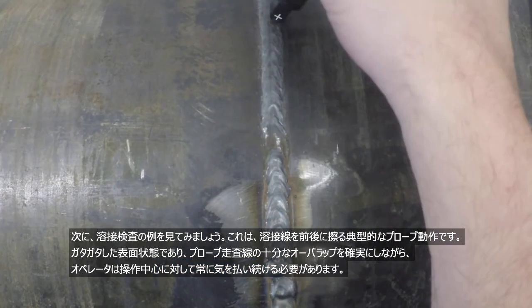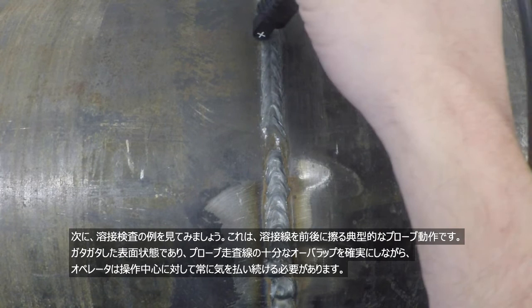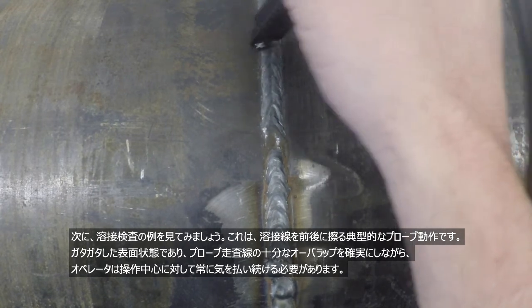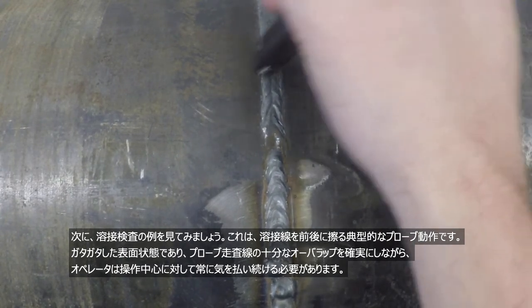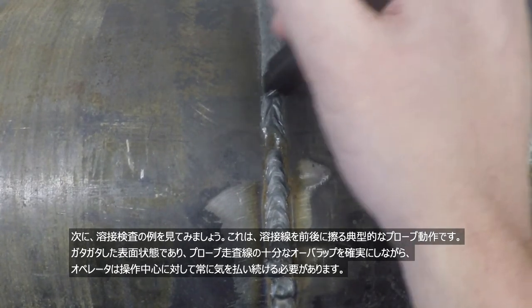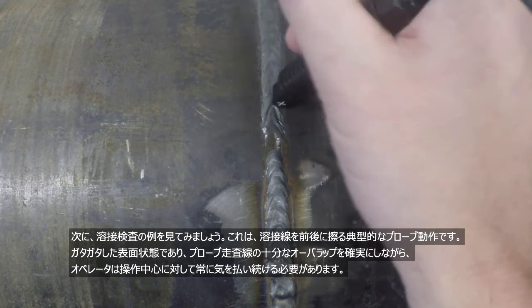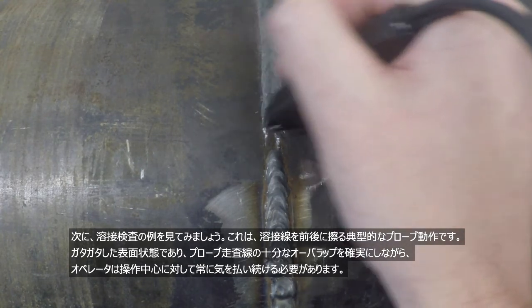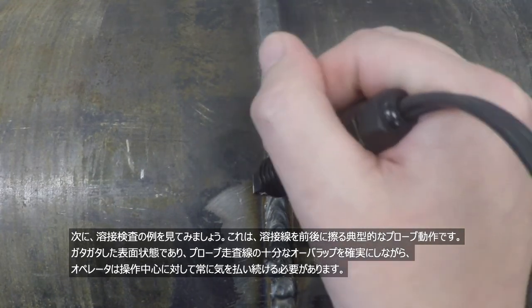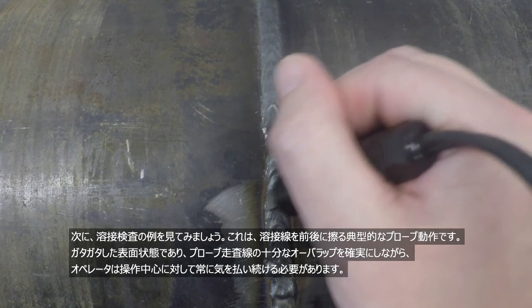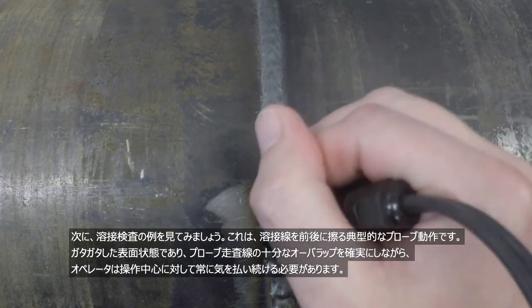Now let's take a look at inspecting the weld. This is a typical case where you have to scrub the weld in a back and forth motion with the probe. This is a rough surface and the inspector really needs to pay attention to their operating point while also making sure they are having enough overlap with their inspection motion.